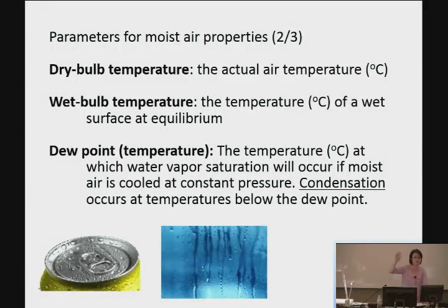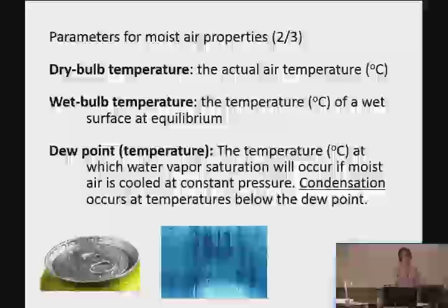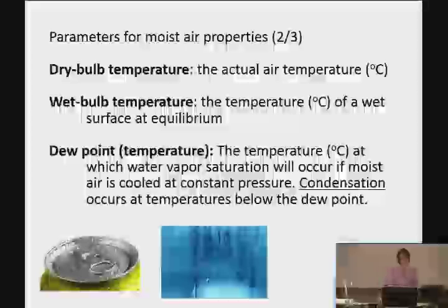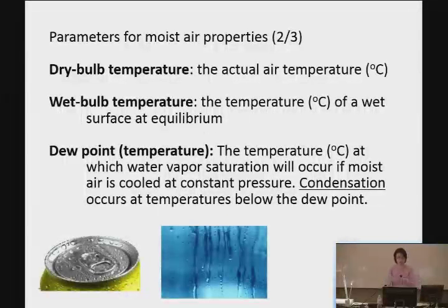It's just that the surface is lower than the dew point, therefore there is condensation going on. Inside the greenhouse may be just 60% humidity, maybe 70% humidity, but because the wall or glazing is lower than the dew point, that's why condensation happens. It's very important to understand.